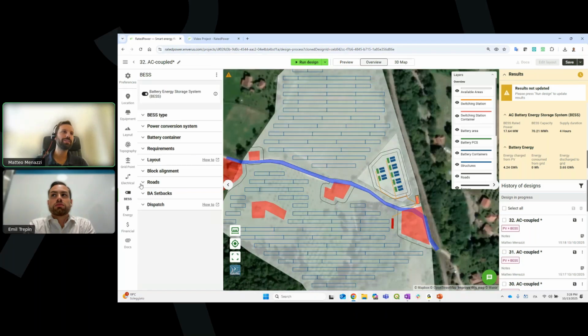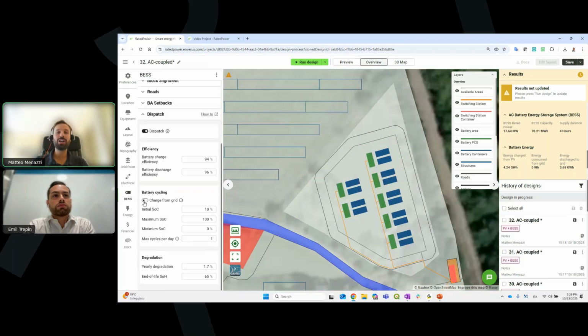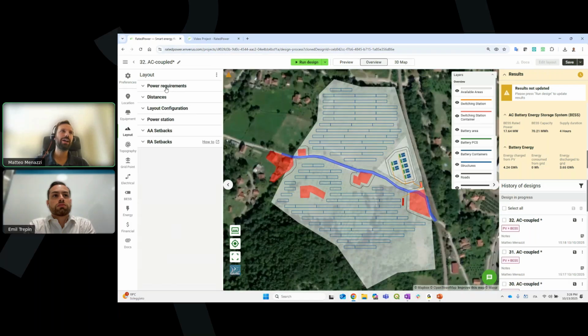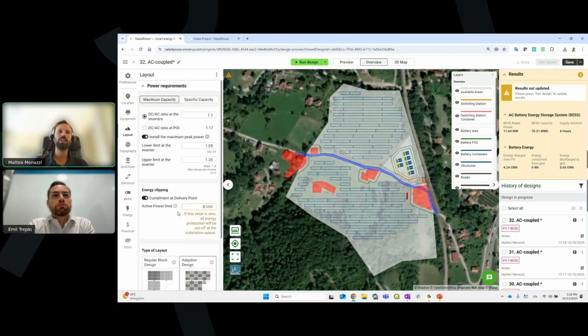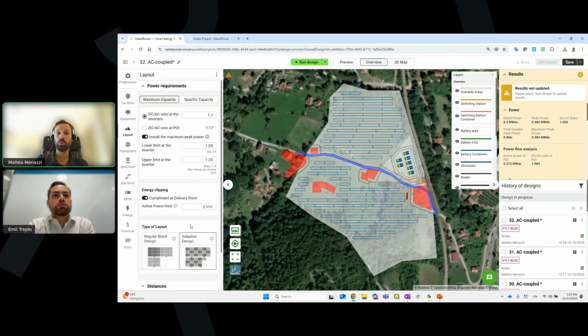You can always decide if you're charging only from the PV or also from the grid. The other thing to consider, under power requirements, is energy clipping. In this example we're producing 3.4 megawatts of power - you can say you cannot inject more than 2 into the grid. So you can account for grid limitations from your grid operator and see how the system performs taking that into account.